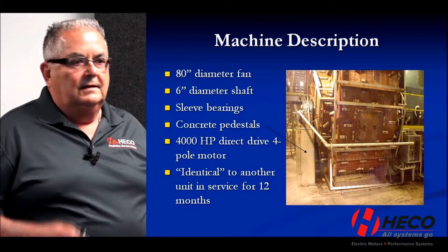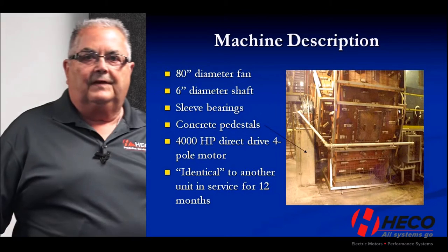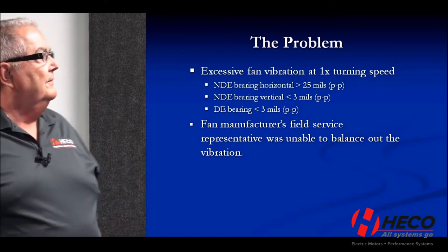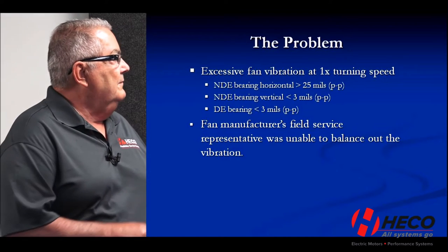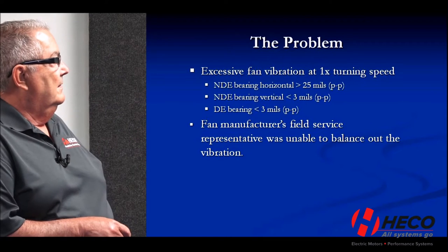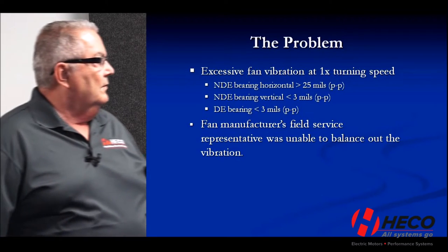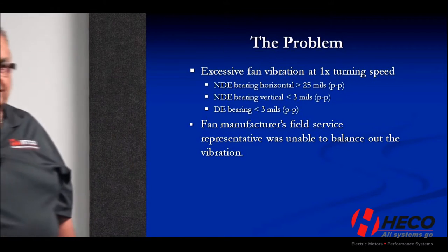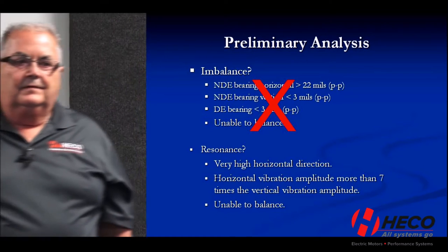They put this second fan in and had a lot of excessive vibration. The field service tech from the fan supplier had been down there commissioning the fan for a number of days, and they called for additional help. The fan had excessive vibration at one times turning speed. The non-drive end bearing horizontal was greater than 25 mils, while the non-drive end bearing vertical was less than 3 mils — very highly directional. The drive-end bearing was also less than 3 mils.